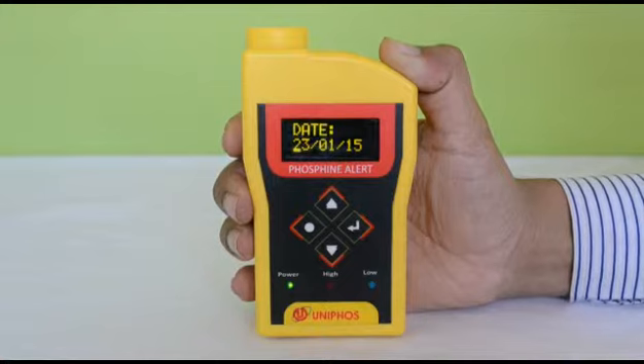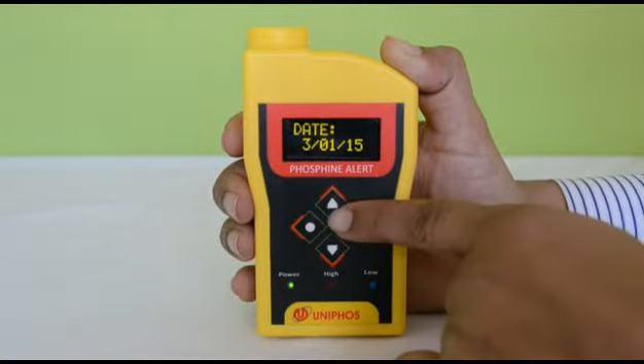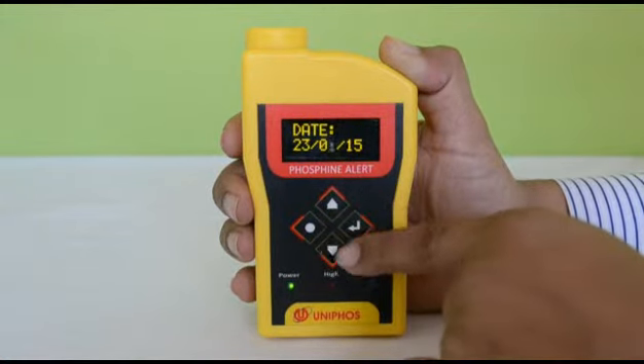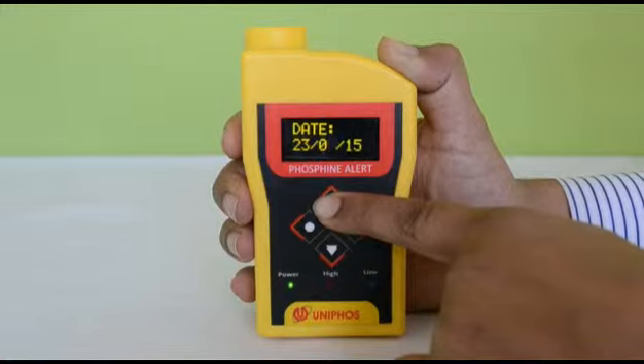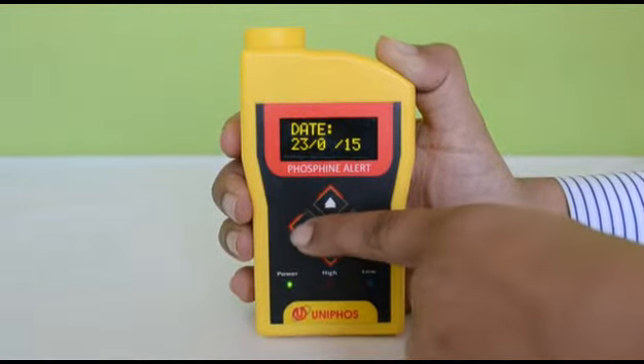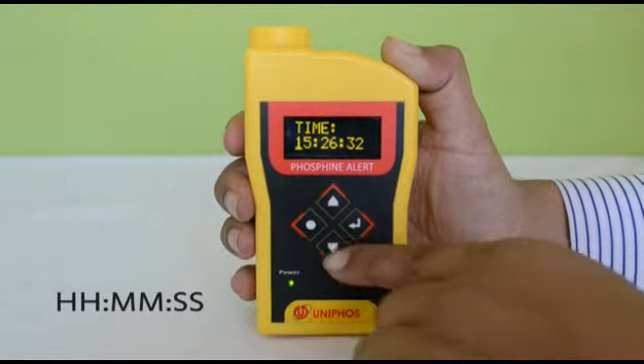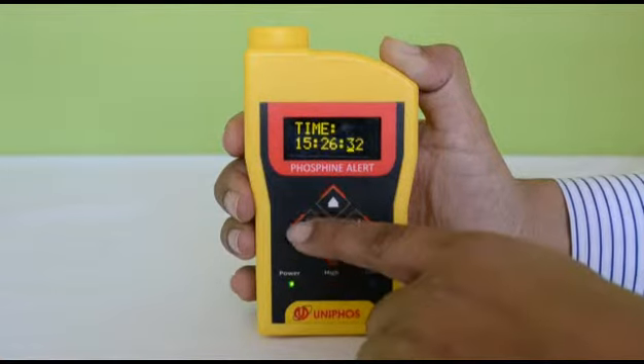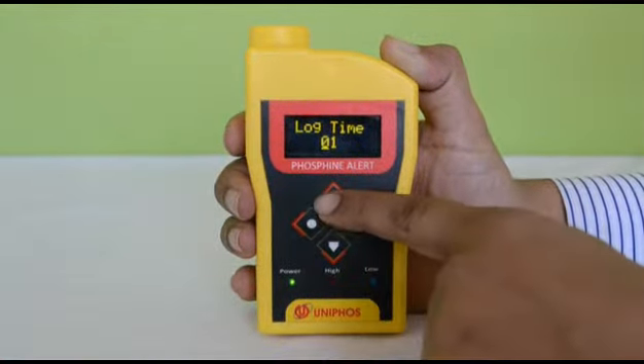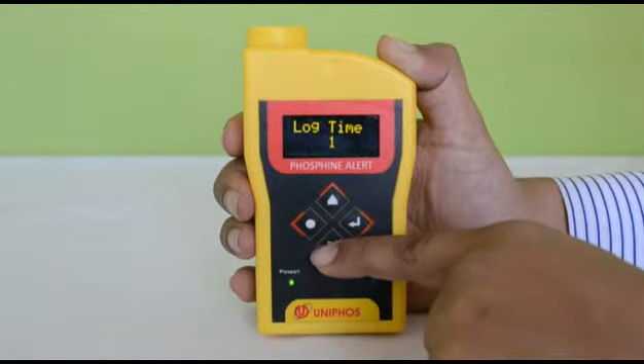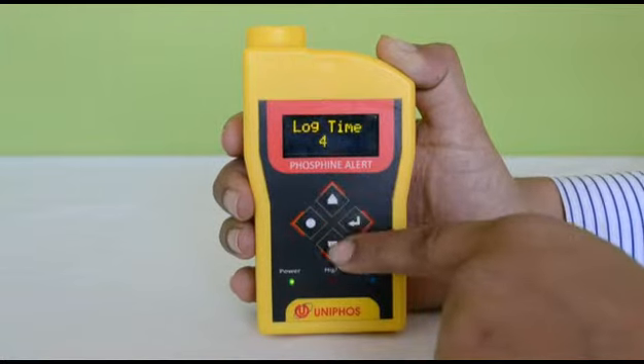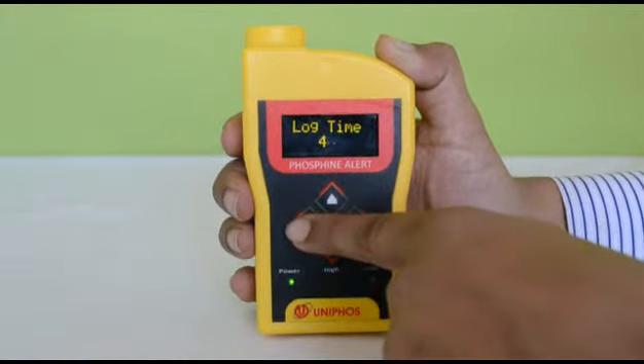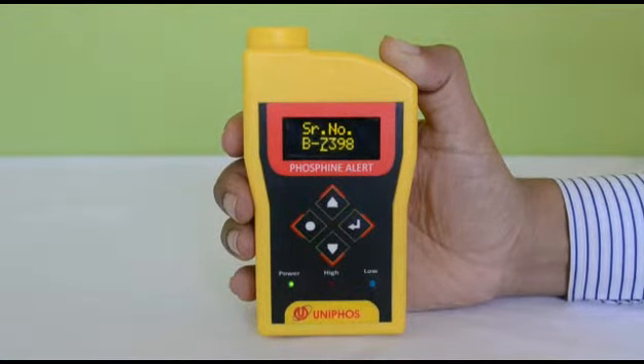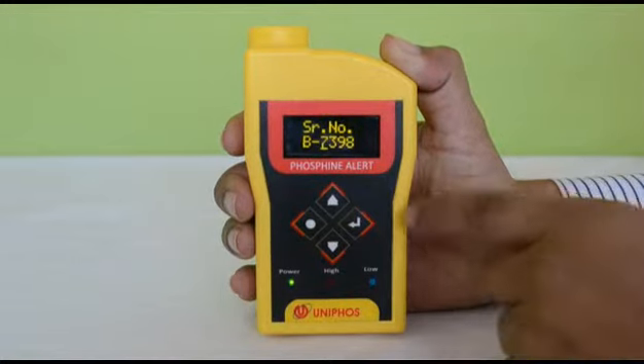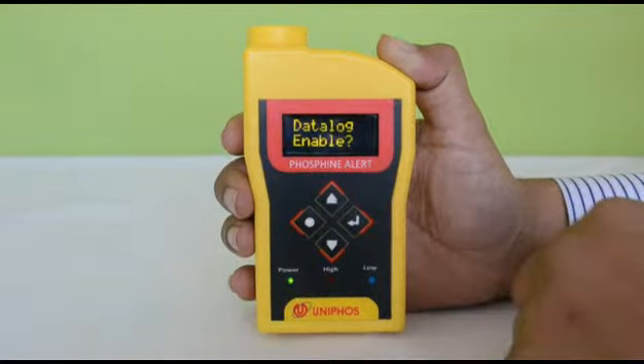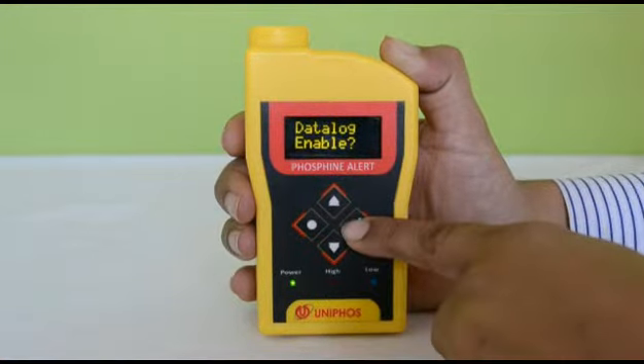The date and time can be set in date, month, year, and hour, minute, second format respectively by using the 4 membrane keys. Log time can be set to any value in between 1 to 99 minutes. Instrument serial number can be set if necessary. Serial number of the instrument is mentioned on rear panel of the instrument. Data logging can be enabled or disabled by pressing enter key or can be skipped by pressing set key.